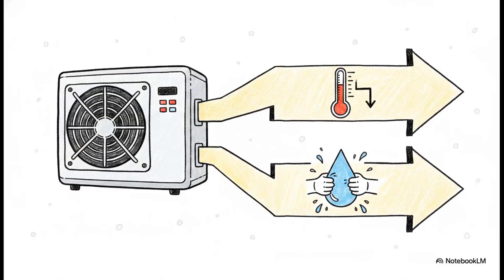So, here's a brilliant fact about air conditioners that a lot of people don't realize. They actually do two vital jobs simultaneously. They remove sensible heat to drop the temperature you actually feel, but they also remove latent heat, which is the hidden moisture suspended in the air. When moisture removal fails, your comfort level completely plummets, regardless of what that digital thermometer says.